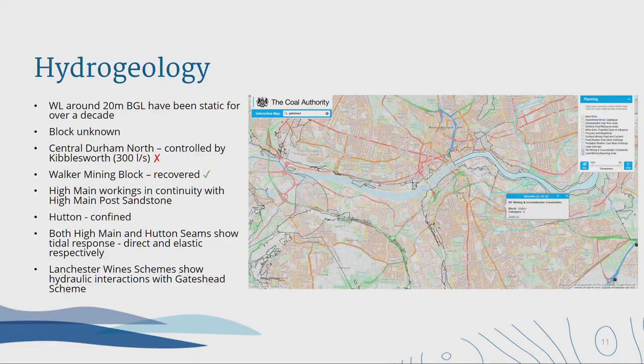We know in this area that water levels have been static for over a decade, around 20 metres below ground level. When we started this project, we didn't know whether the Gateshead site would be in the central Durham North mine water block or the Walker block. Mine water blocks are basically sets of collieries that behave hydraulically in a similar way, so we generally find a similar water level in each set of workings. There is a difference between the Walker block and the central Durham North one, but because we didn't have any monitoring boreholes in that part of Gateshead, we didn't know exactly which block it was in. We've now found out through what we've done that it is in the Walker block.